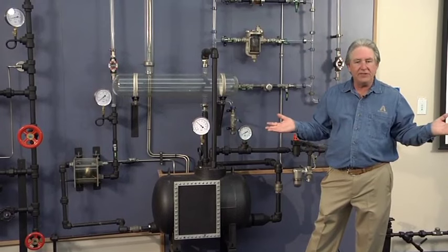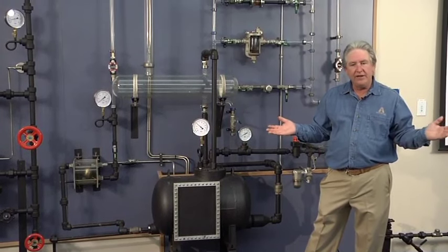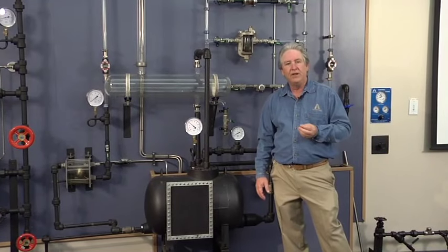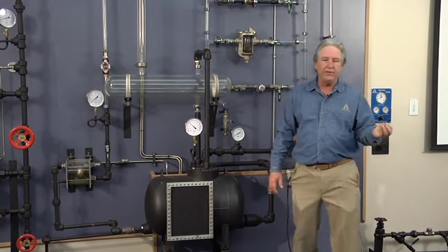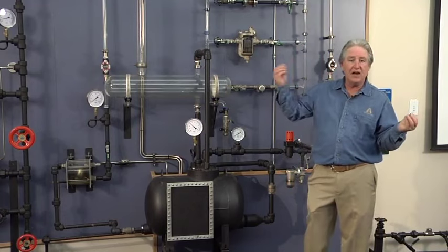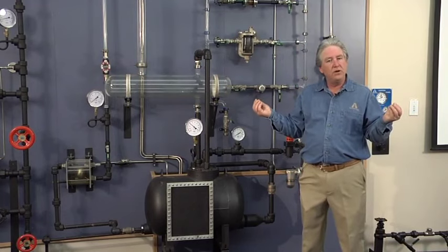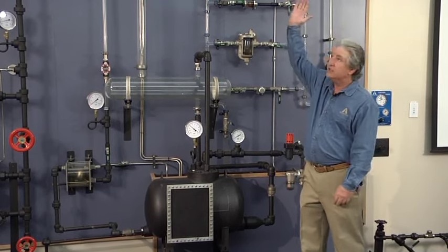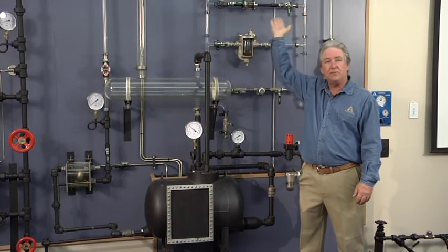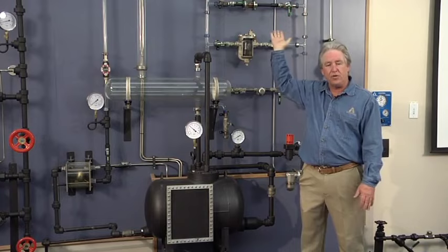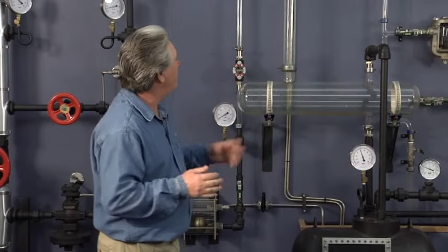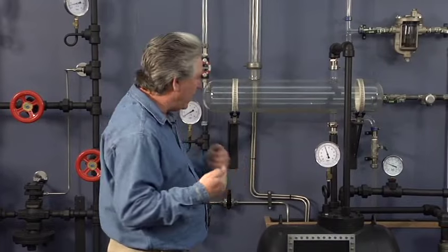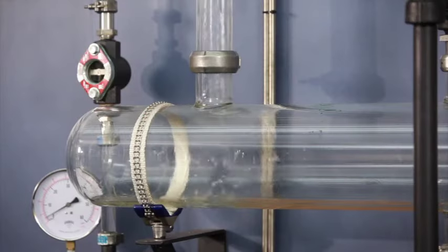Again, as steam experts, we all understand that the latent heat content in lower pressure steam gives us a lot more heat value per pound than does the higher pressure steam. So what it makes sense for us to do is to run those exchangers at the lowest possible pressure to optimize their performance.